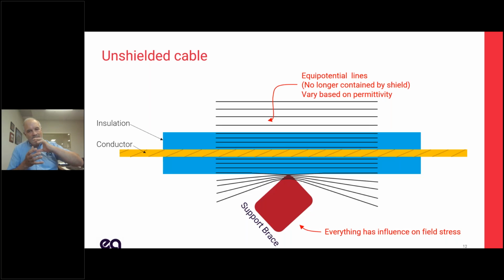That concentration of field is where you run into a situation where the field is now higher, and the insulation withstand of that insulator may not be able to withstand it. Because we don't have a shield, we have to worry about everything around that cable, not just conductors. We have to worry about insulators, the air, pollution and all that. So if we have shielded cables, we're good.